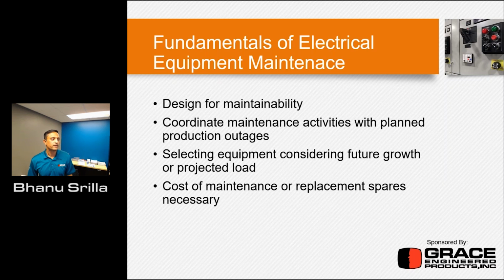So you need to look at the design for maintainability. This is again taken from NFPA 70E, which talks about why you require the electrical equipment maintenance program. Before even the maintenance comes into play, there's a design aspect. When companies put together the design specifications, they need to have design for maintainability criteria clearly defined. A simple example is you don't want equipment that takes about 15 hours to change a small fuse if it requires just 10 minutes. So make sure that things that require maintenance are kept in a place where it's easy to access whenever a maintenance task is performed.